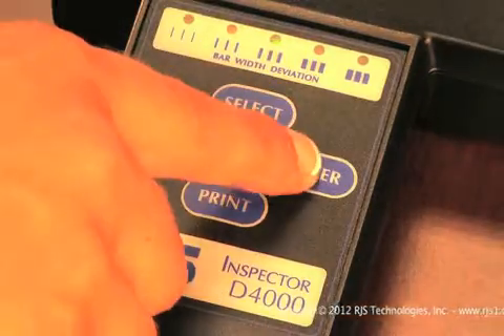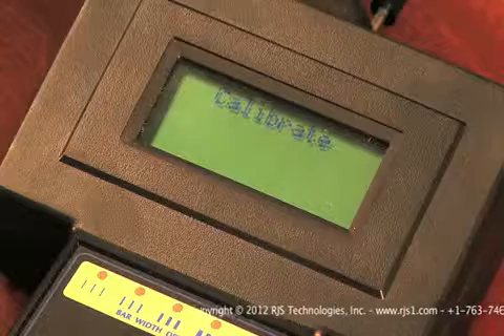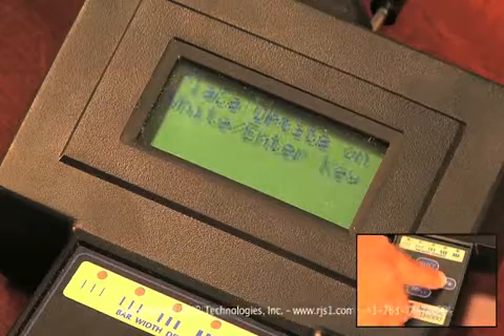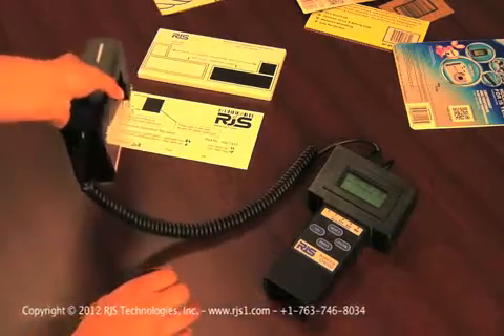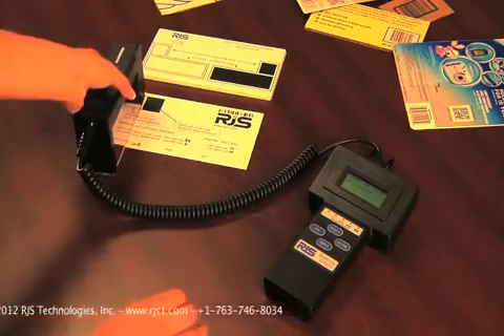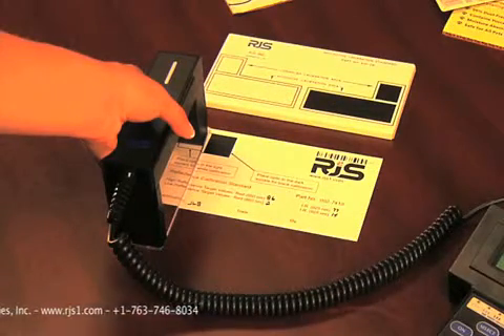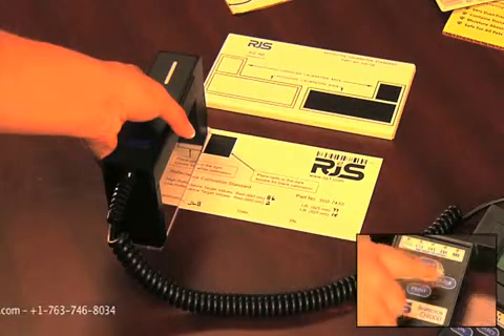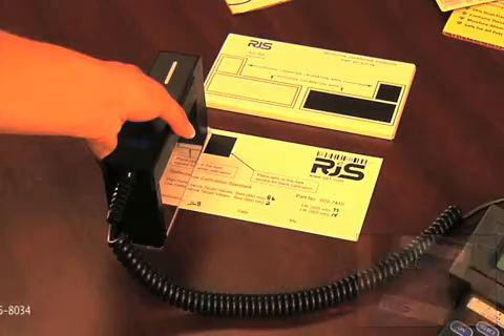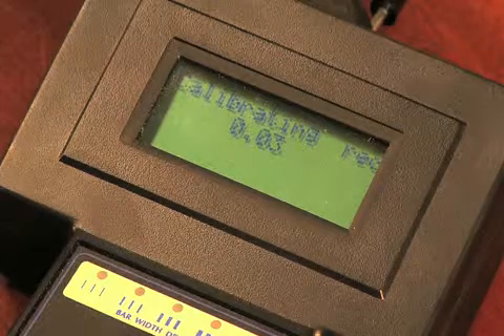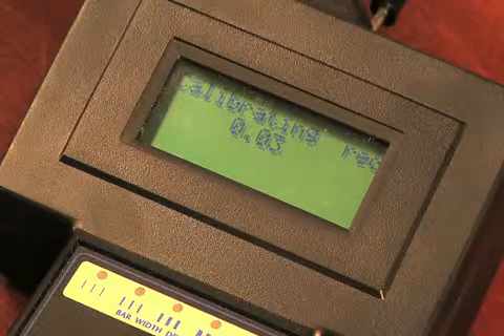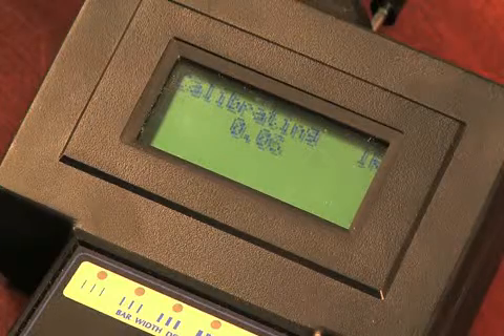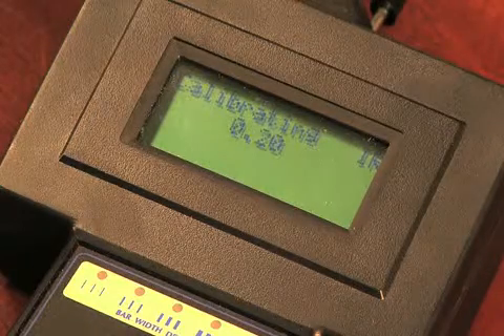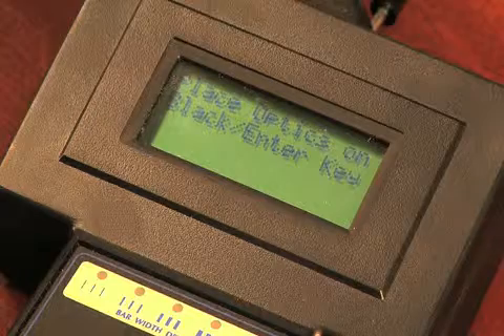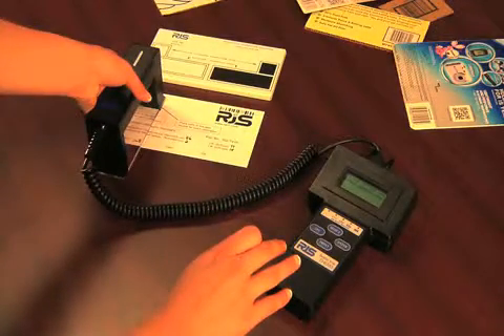Otherwise, press the Enter button, which will bring up Calibrate on the display. Press Enter again, and place the red light of the Auto Optic over the white square. Keep light pressure on the Auto Optic, and press the Enter button. The unit will step through calibration of all 4 apertures, sizes of light, for both the red and infrared light sources. Once it is complete, the display will instruct you to move the Auto Optic to the black square.